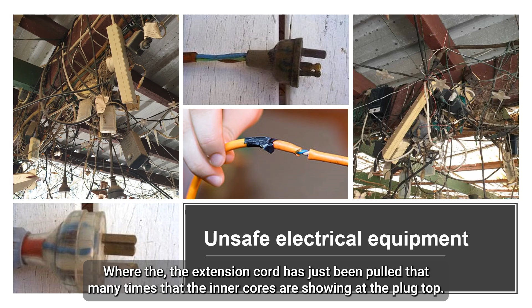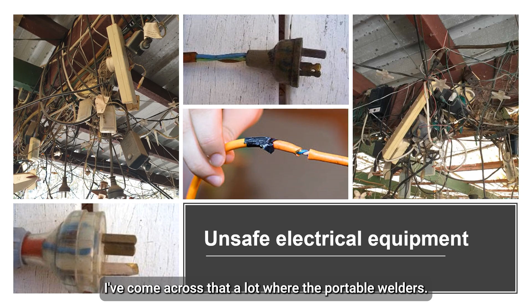I think that one of those shows a plug with the earth pin filed down. This is probably pretty common. I've come across it a lot where the portable welders, oh look, the earth pin's fatter. I know what to do. I'll just cut it down with a grinder and file it back. You can't do this. It's designed for that reason, and that's to allow for bigger fault currents. The other two pictures, that's spaghetti junction, but it could also very easily start a fire, or a heater. So you might want to have the fire brigade on your favorites on your phone.